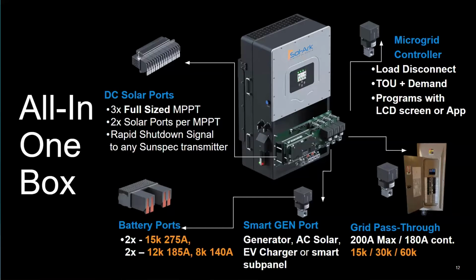Yeah, well, there's a variety of options. I'd say the most popular option is to simply get a 200 amp breaker in a breaker box. That's your utility required external system disconnect, and it's the lowest cost way to do it. On the 15K, we have a breaker for the load side of the inverter, but you need to provide a disconnect on the grid side of the inverter.